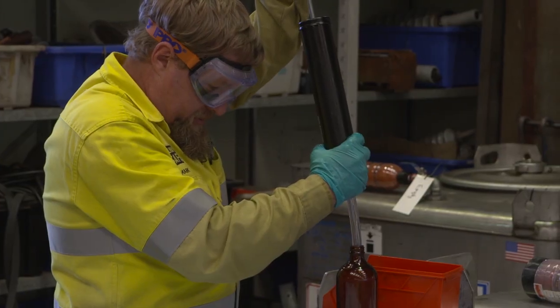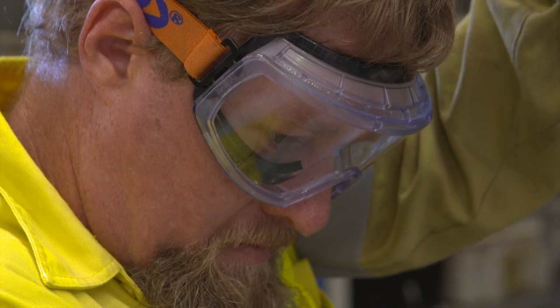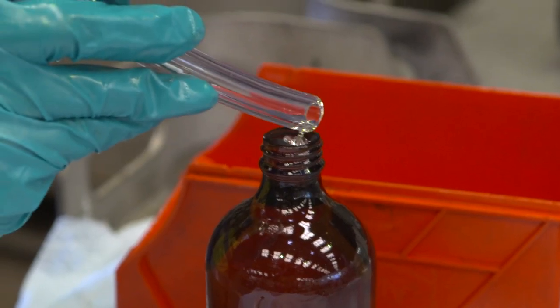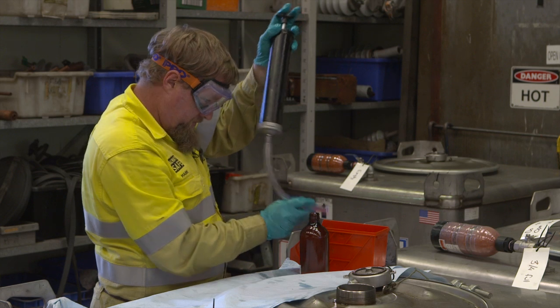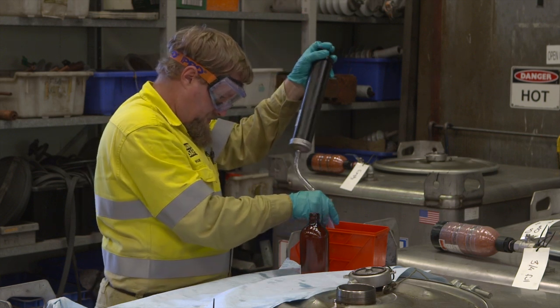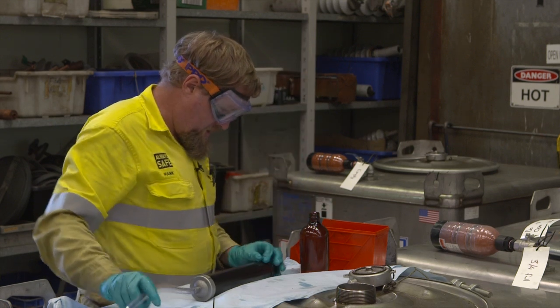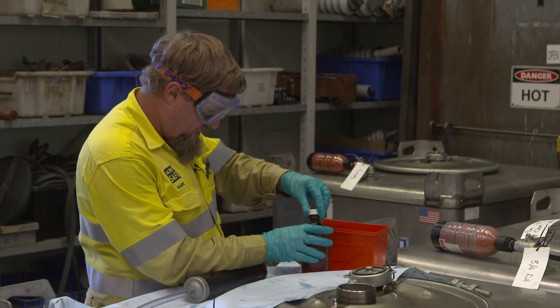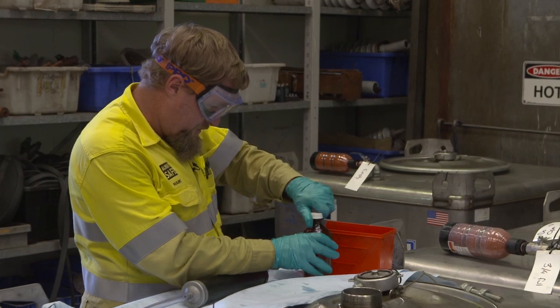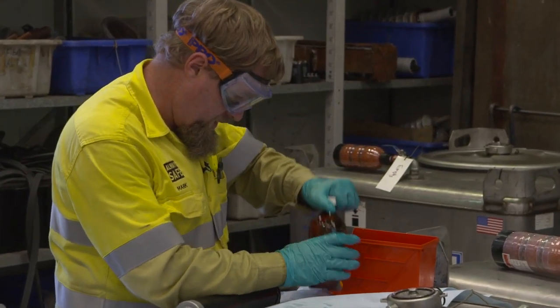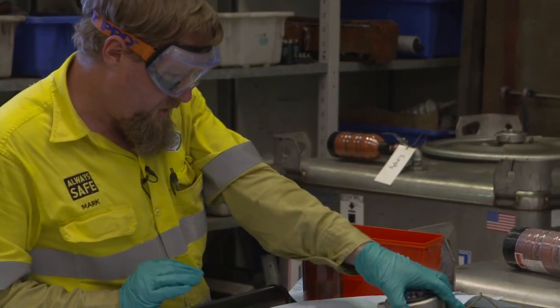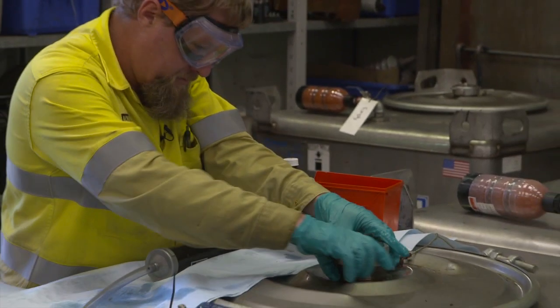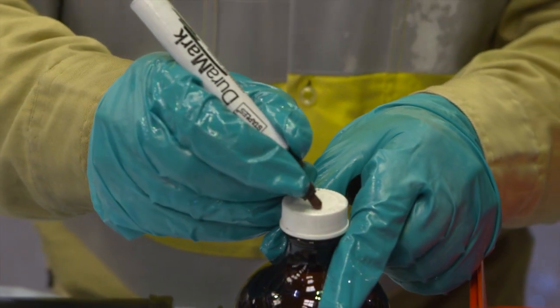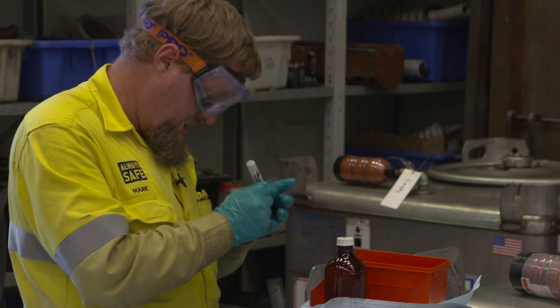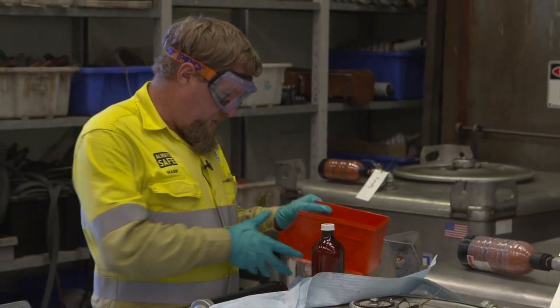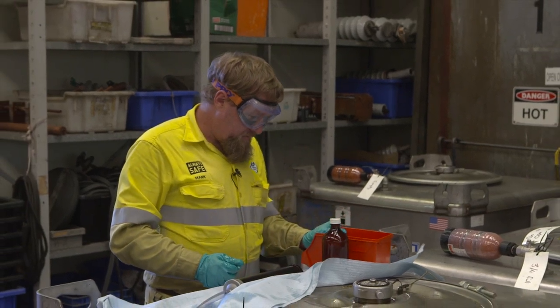Taking the sample, gently push down for the oil to go into the bottle, filling the bottle up. And tighten the lid up, that way there should be no air left in your sample bottle. After finished, put the lid back on. Make sure you label the bottle with the number of the IBC and discard any of the oil that you didn't use in the appropriate oil containers.